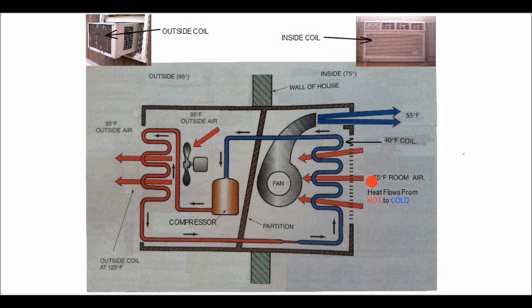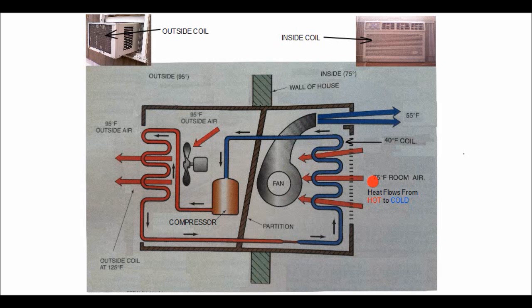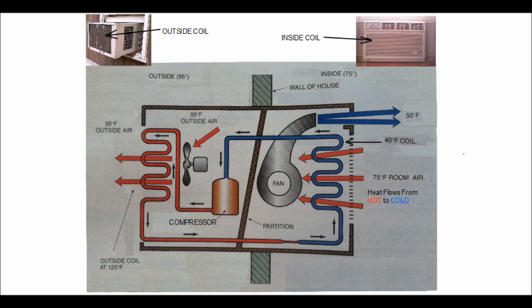But as a rule of thumb, 75 degree air going in, 55 out. If it's 80 degree air going in, then it's going to be 60 degrees out.